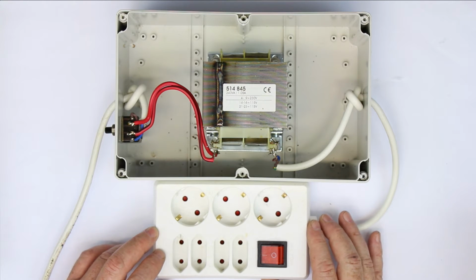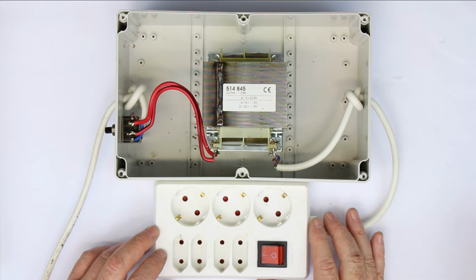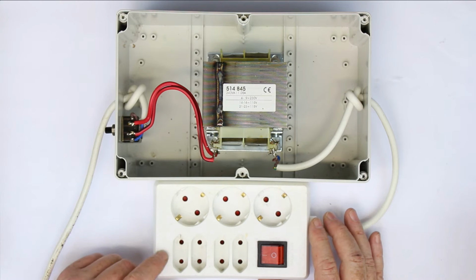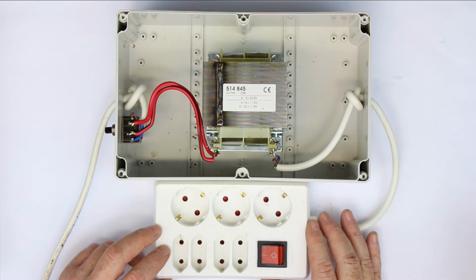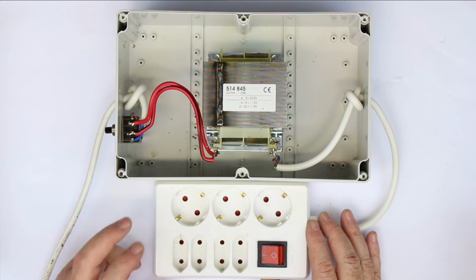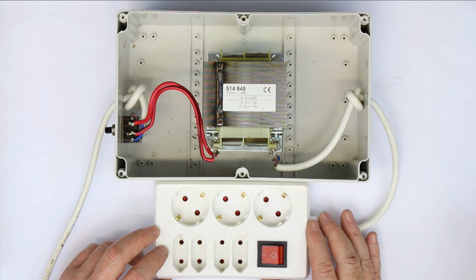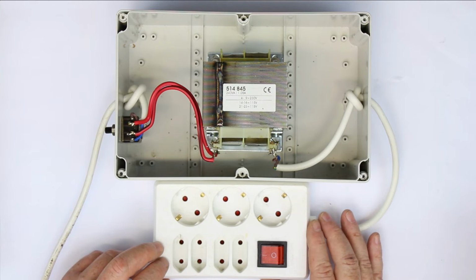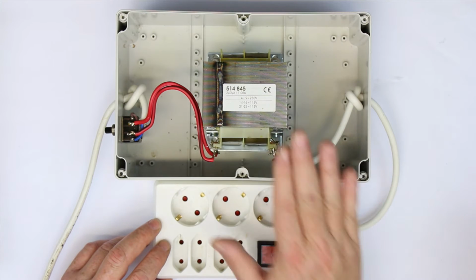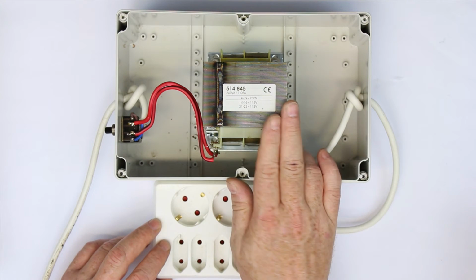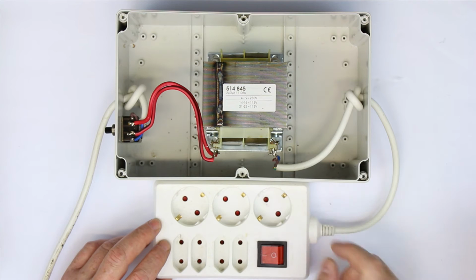But imagine how this is in the lab - you accidentally touch the live wire in your powered device, and you constantly have to run to the fuse box just to reset the ground fault circuit interrupter. So first for safety reasons, and second for convenience, it's much better to have such an isolation one-to-one transformer.